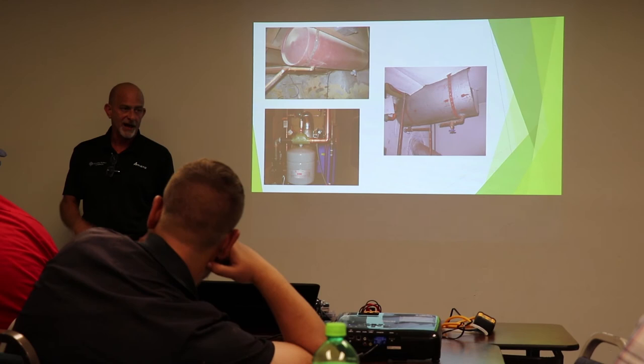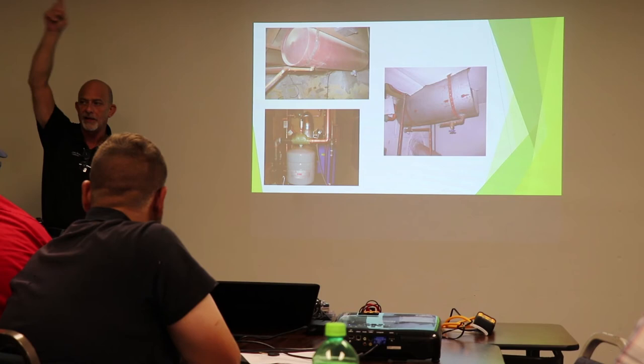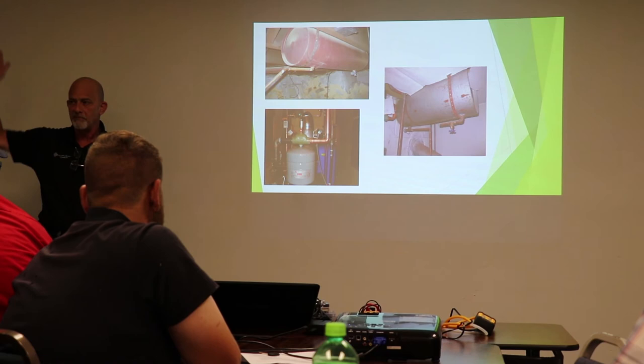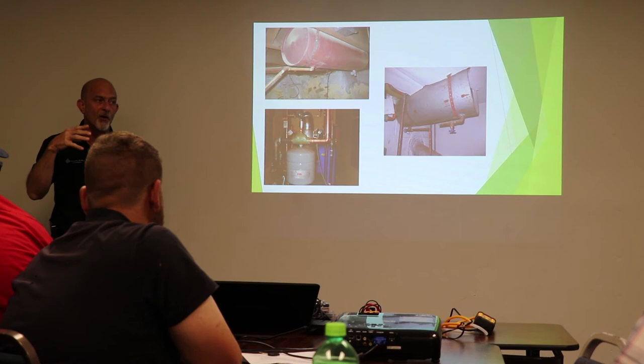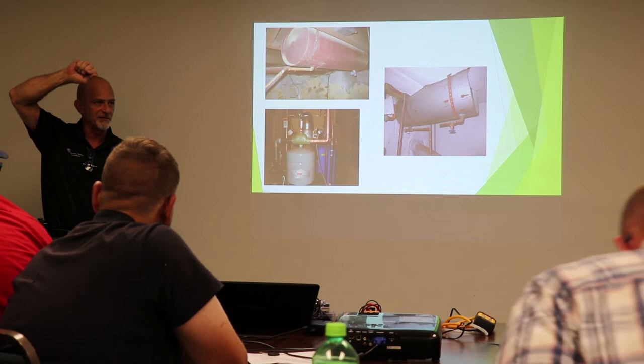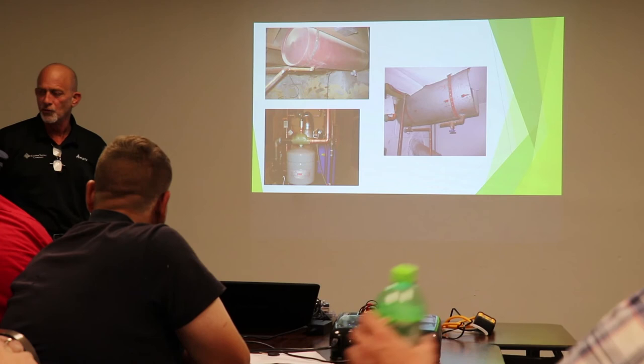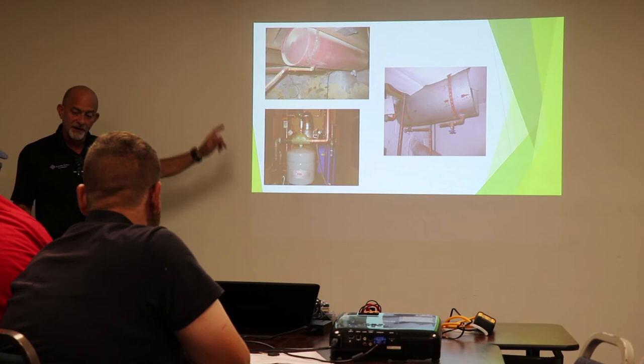Anybody seen an old wall radiant, ceiling radiant system with copper tube? A lot in Chicago, and the manifolds were up in a closet somewhere. Now, these are going back 30, 40 years. So what do you think those shutoff valves and balancing valves after 40 years look like? They're rusted. So many people have had screwdrivers on them. You can't move them.